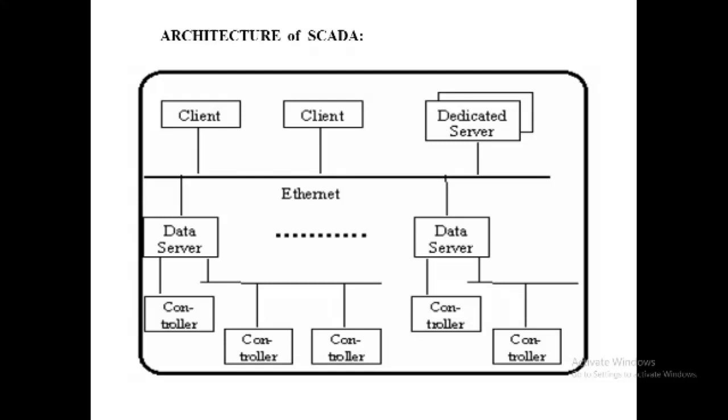Now, the software architecture. SCADA products are multitasking and are based upon a real-time database, that is RTDB, located in one or more servers. Servers are responsible for data acquisition and handling, like polling controllers, alarm checking, calculation, logging, and archiving on a set of parameters, typically those to which they are connected. However, it is possible to have a dedicated server for particular tasks, for example historian, data logger, or alarm handler. This is a generic SCADA architecture for the product.